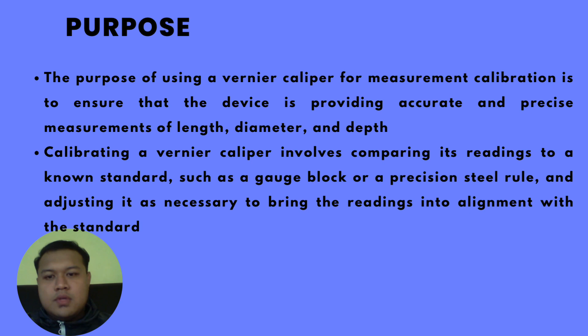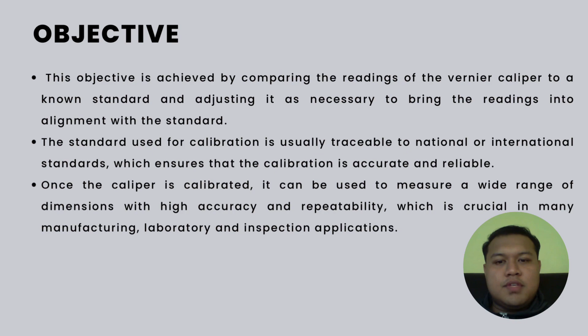Okay, next is the objective. This objective is achieved by comparing the reading of the Vernier caliper to a known standard and adjusting it if necessary to bring the reading into agreement with the standard. The standard used for calibration is traceable to national and international standards, which ensures that the calibration is accurate and reliable. Once the caliper is calibrated, it can be used to measure a wide range of dimensions with high accuracy and repeatability, which is crucial in many manufacturing and laboratory inspection applications.